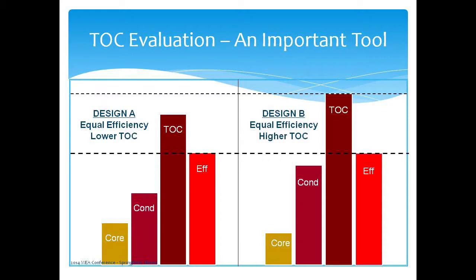There's a difference in the core material and the conductor between both of them. You can see that the total owning cost for design B is actually higher than design A, even though both meet the efficiency level. One reason is that this design has more material on the core side, which keeps the cost down, while this one has less material on the core side. You can see how the total owning cost is impacted by the ratio of core and conductor. Just be thinking about this if you're looking at designing and changing over for DOE 2016.